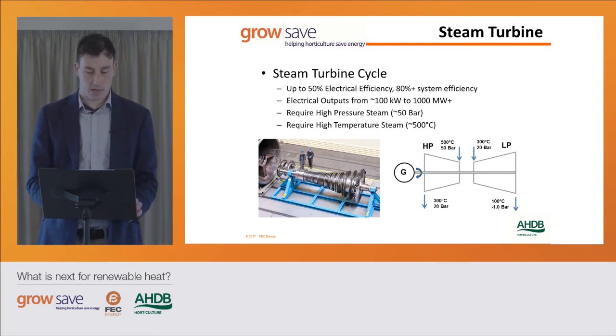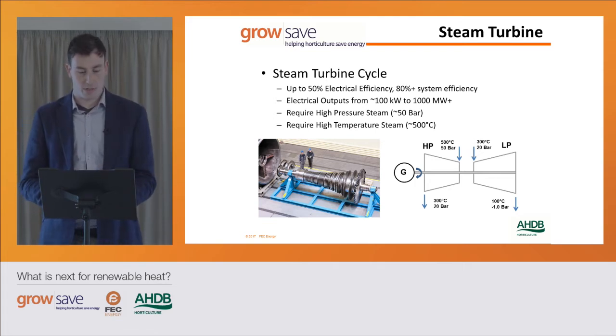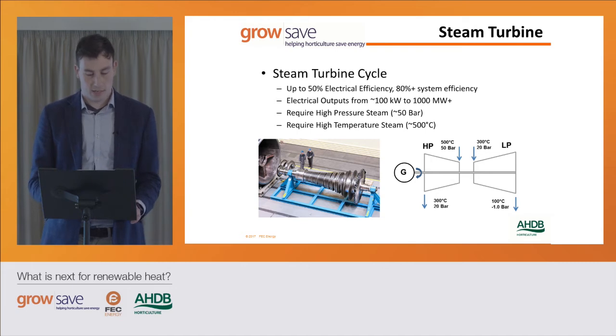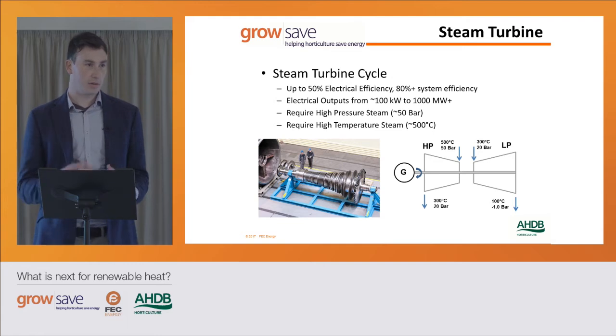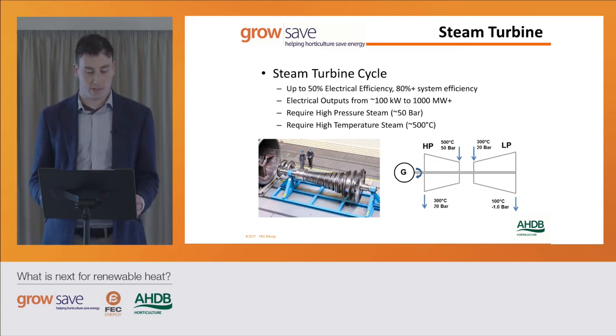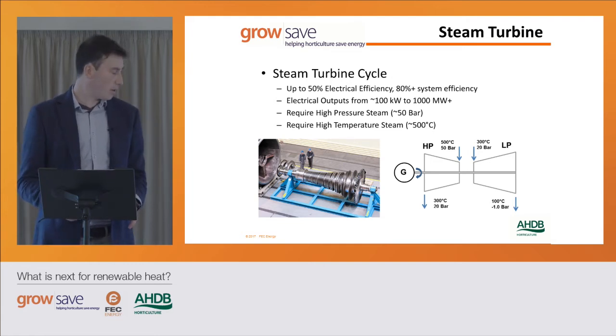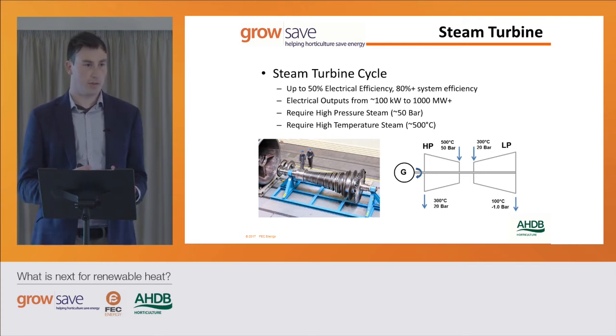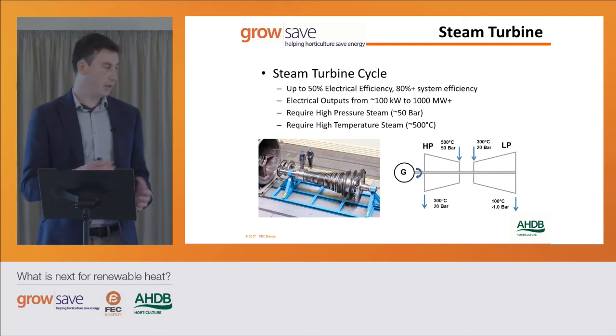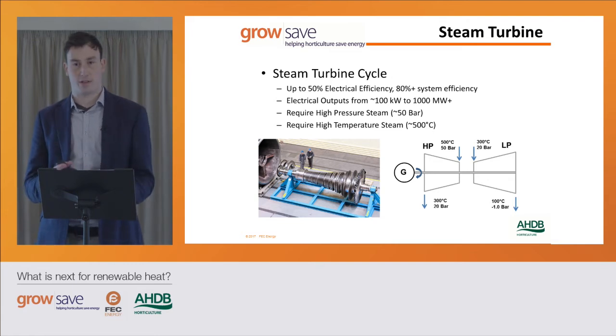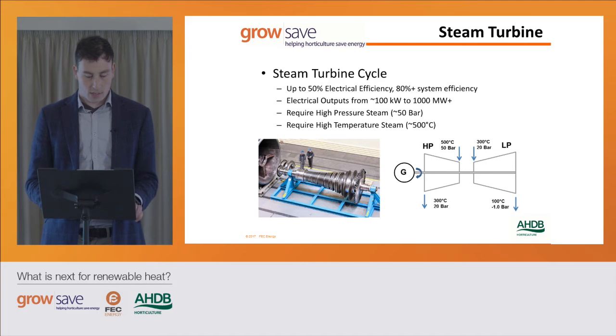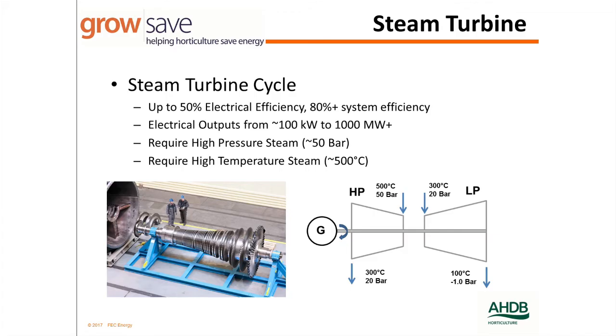Steam turbines are relatively straightforward and a well-proven technology. The requirements are steam, generally at quite high pressures, around 50 bar, 500 degrees C. The turbine extracts all the thermal energy from that steam, often in numerous stages designed for specific temperatures and pressures as it goes through. They operate at fairly high speeds, especially compared to other turbine types like a hydro turbine or wind turbine—more like engines in that regard.